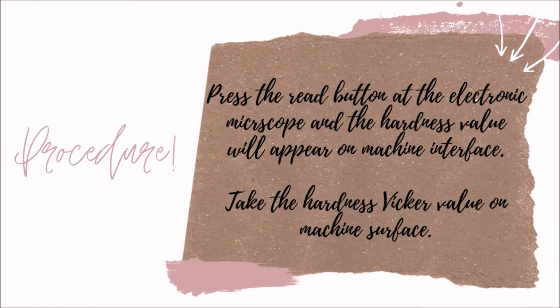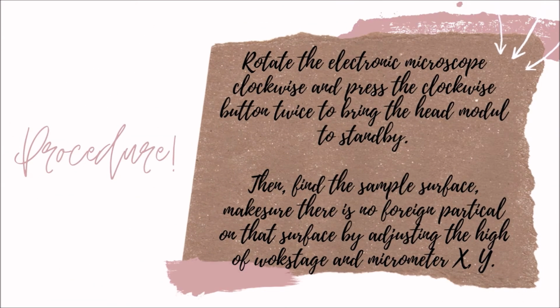Press the read button on the electronic microscope and the hardness value will appear on the machine interface. Take the Vickers hardness value from the machine. Rotate the electronic microscope clockwise and press the clockwise button twice to bring the head module to standby. Then find the sample surface. Make sure there is no foreign particle on that surface by adjusting the height of the work stage and the micrometer X and Y.